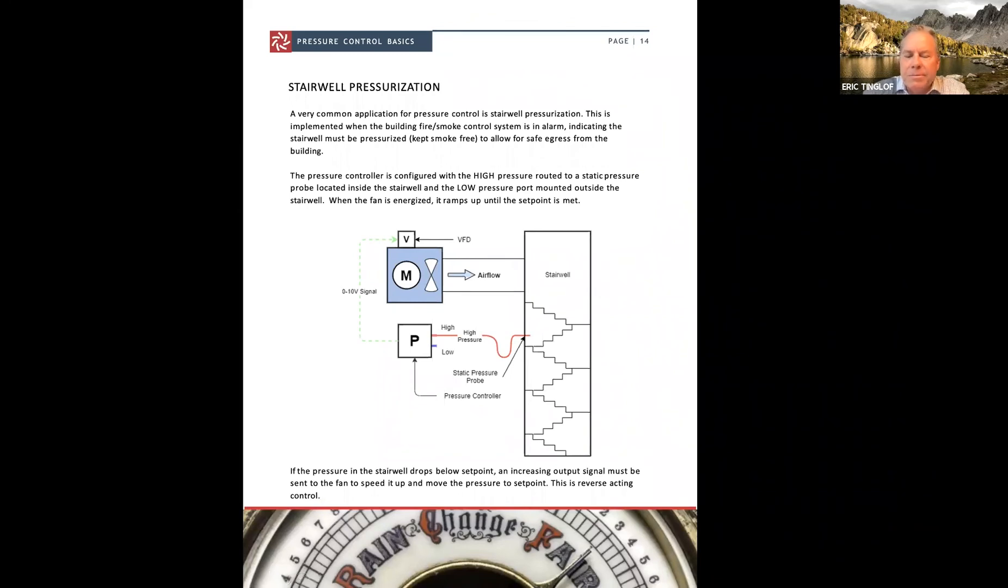Stairwell pressurization. You have the high pressure port via a static pressure probe mounted in the stairwell. We're trying to keep this area positively pressured. This is to atmosphere. So as the pressure goes down in the stairwell below a set point, then we send a signal back to the motor to speed up. Again, reverse acting control.